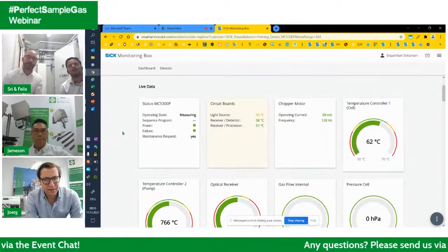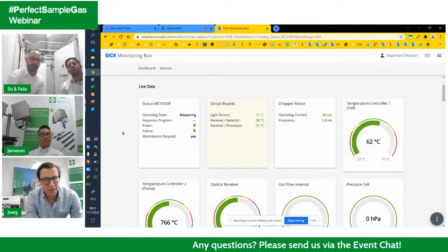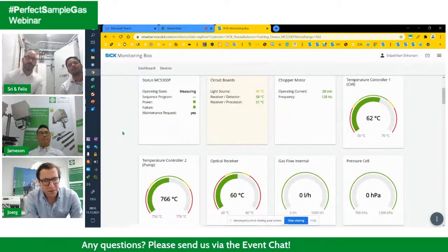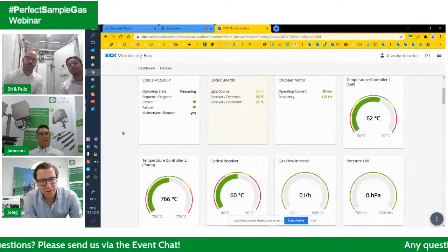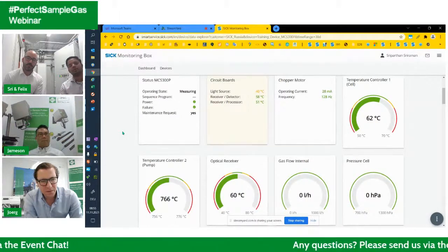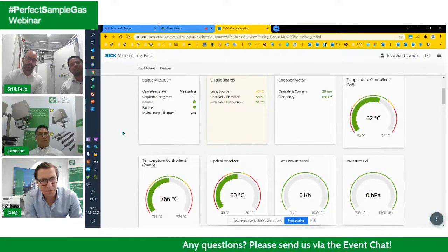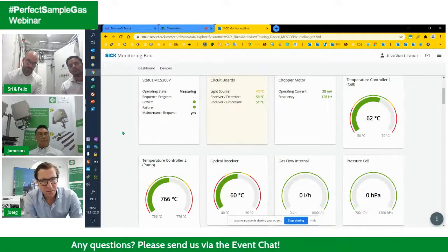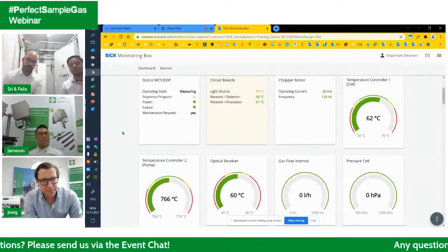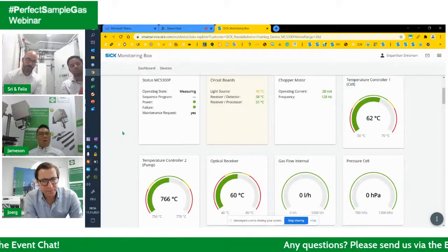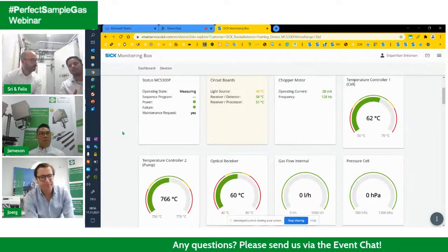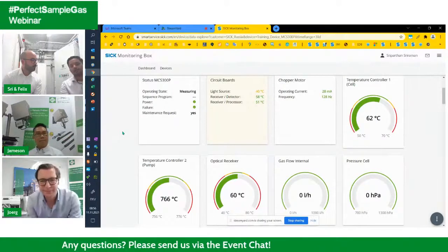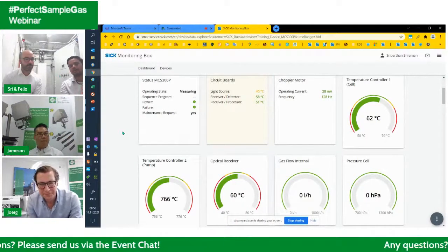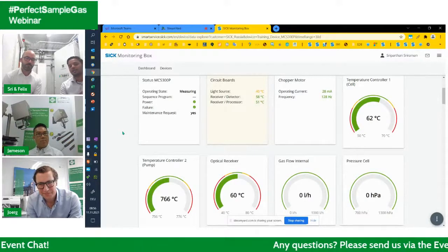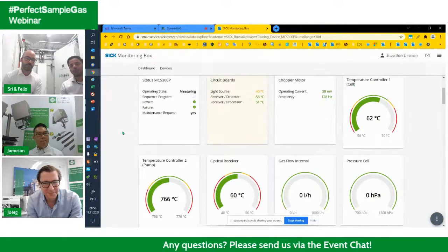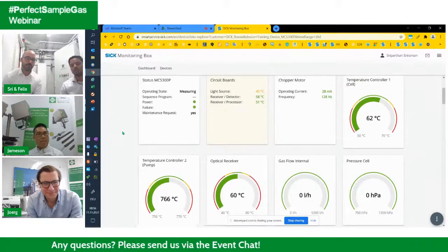And the fact that we are doing the system integration of the complete solution, we are able to understand the cause and effect within the complete solution, right from the sampling point until the data reporting. We are able to understand when an error happens, what would be the possible causes. So if there is a reduction of pressure in a cooling circuit, we will be able to provide certain prompts in the system that say, 'hey, maybe you want to check the pressure in the cooling circuit—maybe there is a leakage, a pressure drop, or a blockage somewhere.' This already preemptively helps both the customer and our service technicians to troubleshoot from a remote location.